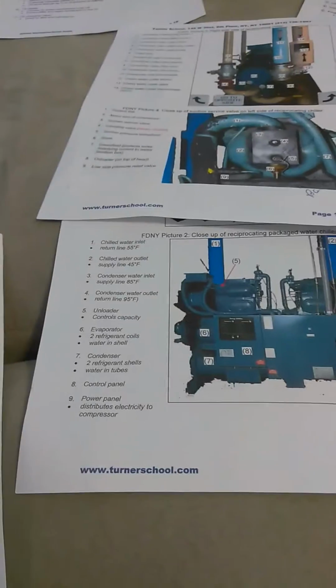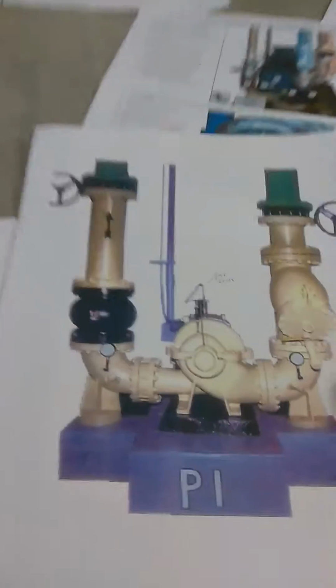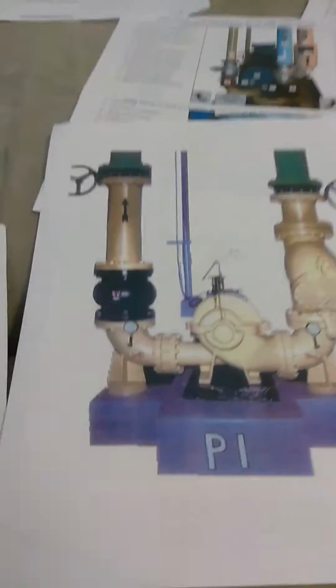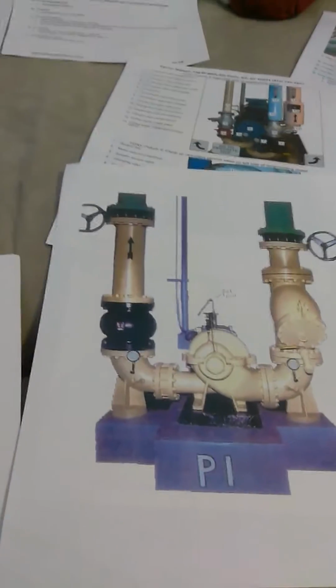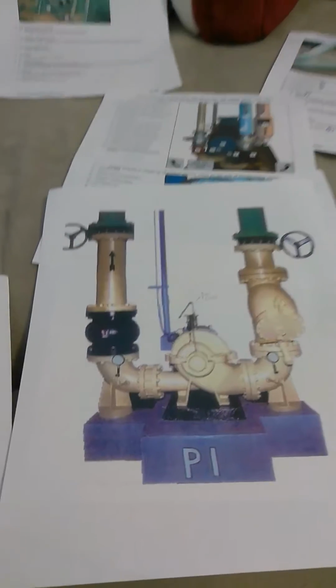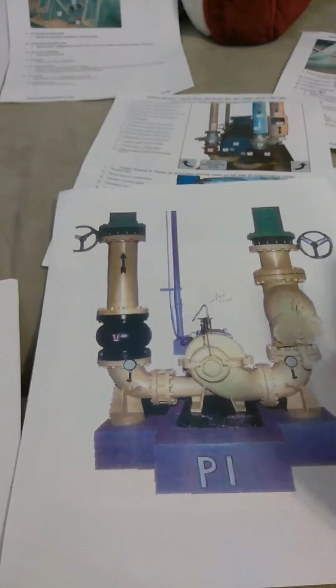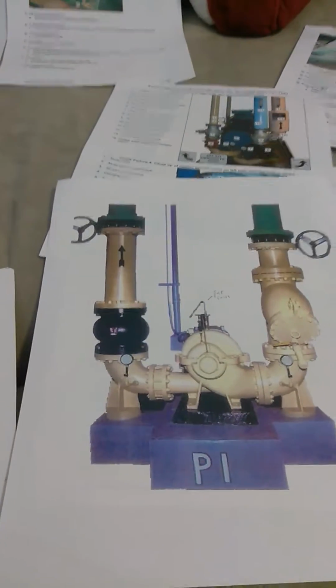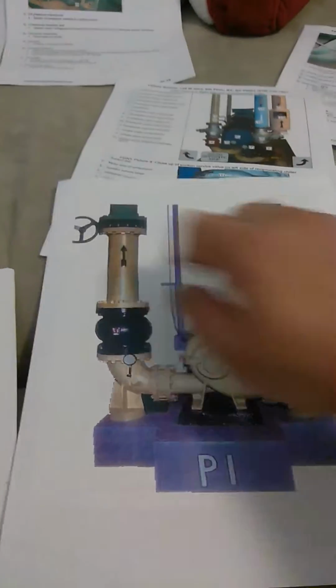Alright, now you go to your pumps. I mean, it all makes sense. Check the chiller, the tower, then you go to your pumps. Check the suction strainer. Make sure to clean it if you have to. Open the suction valve. Close the discharge valve.